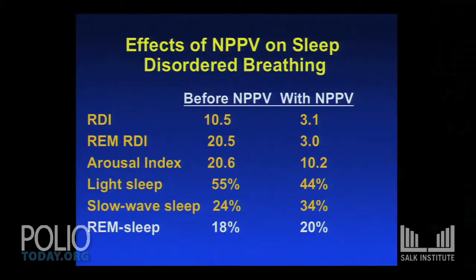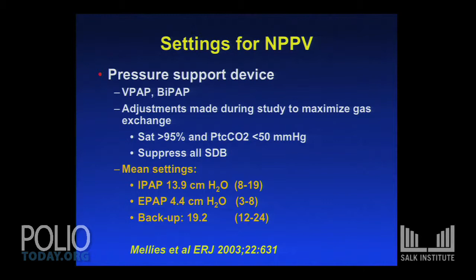In a study by Mellies in the European Respiratory Journal, in a group of mixed neuromuscular diseases, some post-polio, some ALS, some myopathies, they used bi-level type devices. They made adjustments with sleep studies, and what they found was that the mean settings for the machine were an inspiratory pressure of about 14 centimeters of water, expiratory pressure of about 4, and the backup rate was fairly high at around 19. That may have been to do with some of the types of patients that they have. We haven't found that we need that high a backup rate, but it shows you that the pressures that you need are moderately high and can be quite high in some patients.